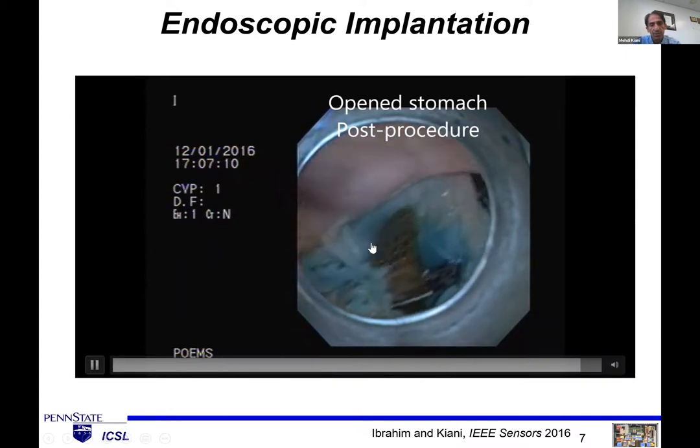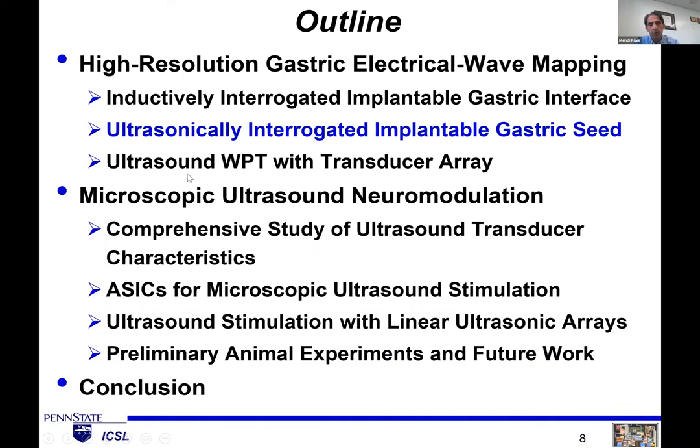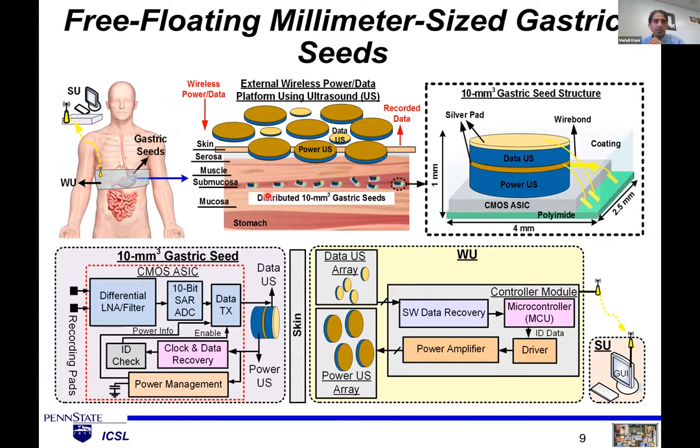We call the new system the gastric seed. Instead of a centralized device, we propose many small devices, each the size of a grain of rice — around 10 millimeters cubed — implanted into the submucosal layer wherever needed to record gastric slow wave activity and transfer data out. The main challenge is powering and communicating with such small devices. That's why we chose ultrasound, which is better suited for larger depths and smaller device sizes. We use ultrasound for both powering and communication.